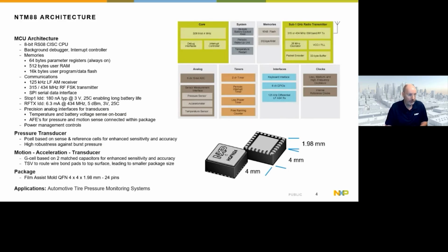The pressure transducer itself is based on what's known as P-cell technology, essentially the buildup of an electronic diaphragm, so that as pressure changes we get a capacitive change in the signal, and that's what we're measuring. It offers very high robustness against burst, which is an industry problem for pressure sensors in general.